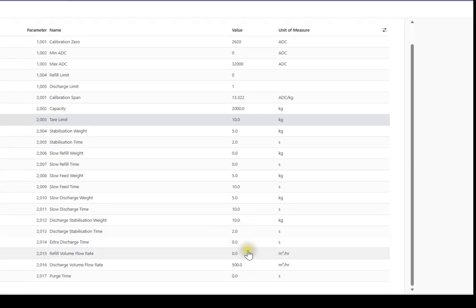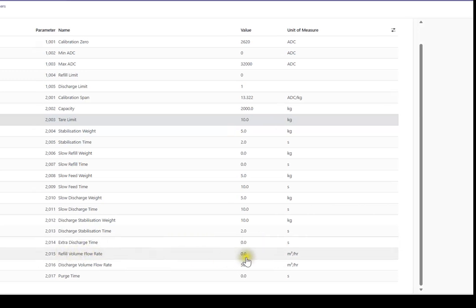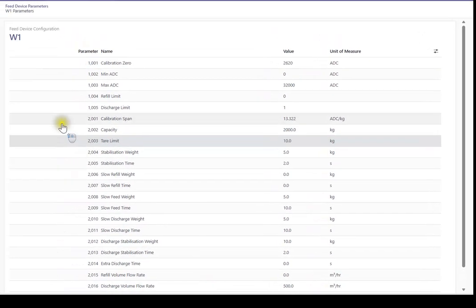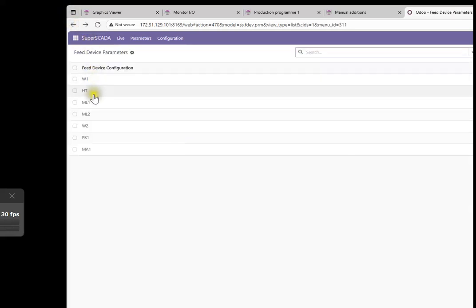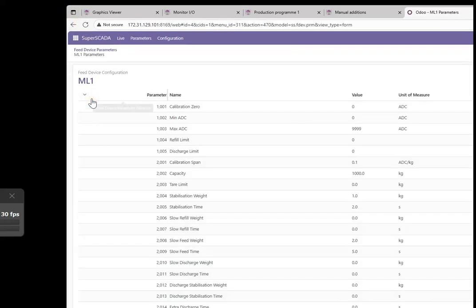If I just scroll down a bit more, the extra discharge time is not relevant here, but on some sites you can ask for extra stabilization time, extra discharge time after it finishes its discharge. The refill volume flow rate won't be used because it's not a refilling scale, and the discharge volume flow rate is to do with simulation. The purge time, I'll come on to that in a moment for liquids, but it's not used for normal weighing in scales. So if I go back and then go to ML1, now ML1 is a mixer liquid.